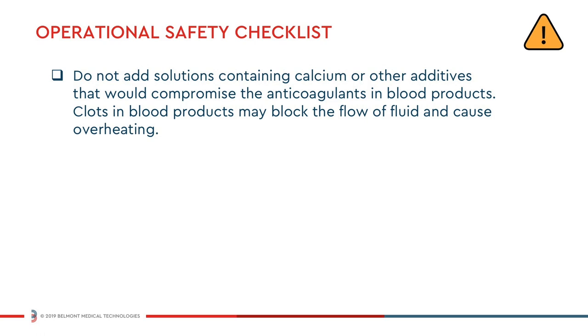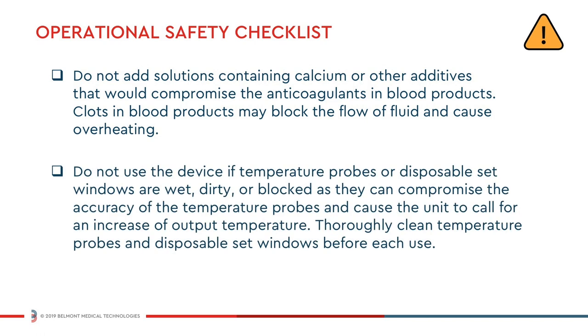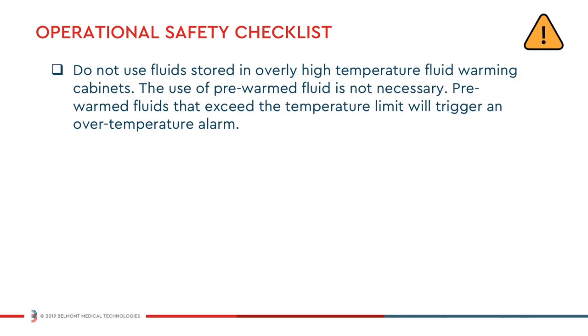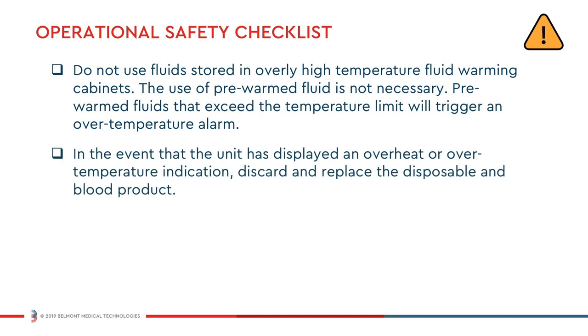Do not use the device if temperature probes or disposable set windows are wet, dirty, or blocked, as they can compromise the accuracy of the temperature probes and cause the unit to call for an increase of output temperature. Thoroughly clean the temperature probes and disposable set windows before each use. Do not use fluids stored in an overly high temperature fluid warming cabinet. The use of pre-warmed fluids is not necessary. Pre-warmed fluids that exceed the temperature limit will trigger an over temperature alarm. In the event that the unit has displayed an overheat or over temperature indication, discard and replace the disposable and blood product.